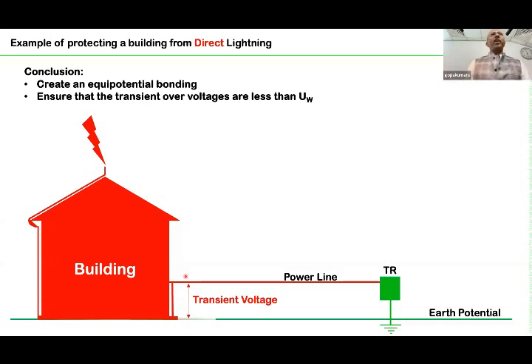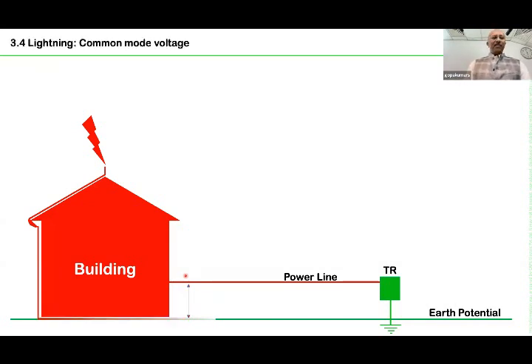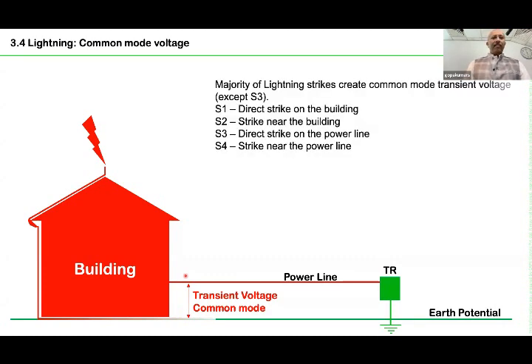So you don't need to be worried, thinking that the SPD is diverting the current to the line and, as a result, my neighbors will be in trouble. Not like that. Otherwise also the neighbor will be in trouble. And normally, it's a common mode phenomenon, because in case of a direct lightning strike on the building, a common mode phenomenon means the potential of all the four wires, like line, three phase and neutral, is going up with respect to earth.